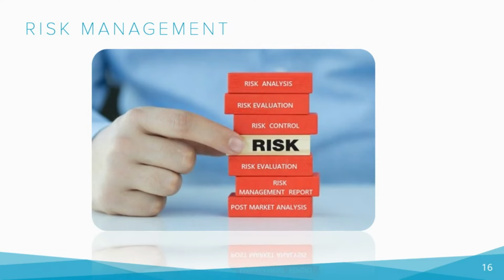To ensure that medical device manufacturers meet the requirements of the EU MDR, they must implement a risk management process that conforms to the international standard for medical device risk management, which is ISO 14971. This process must be integrated into the manufacturer's QMS and must be documented and kept up to date throughout the device's entire life cycle. Critical components of the risk management process are the identification of hazards related to the device, the assessment of the risk posed by those hazards, and the implementation of risk control measures to mitigate those risks to an acceptable level.